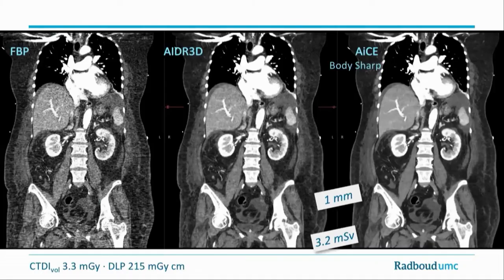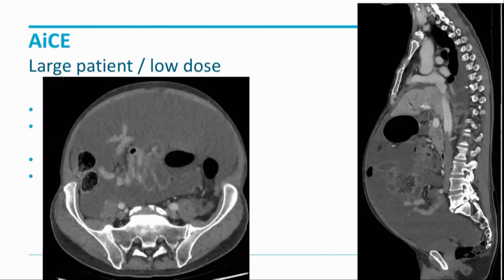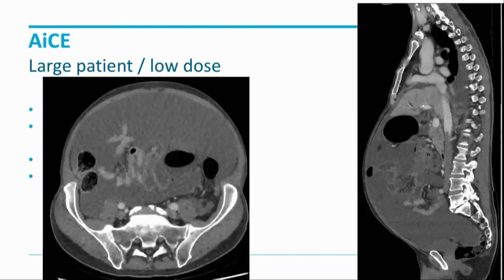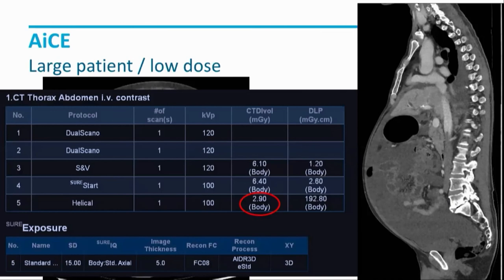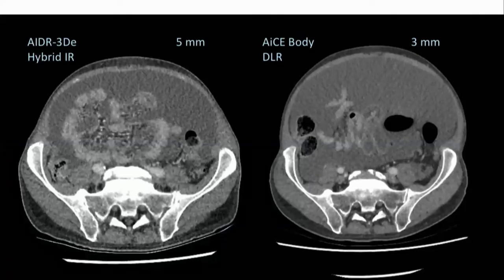This can be organ-specifically optimized. With the newest high-end regular scanners, at a dose of 3.2 millisievert, one millimeter sections, we get excellent image quality — even for large patient sizes at 100 kV, 2.9 milligray CTDI — and still excellent quality. Compared to regular scanner five millimeter images, deep learning outperforms that by far.